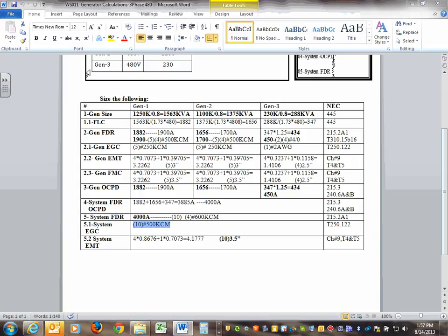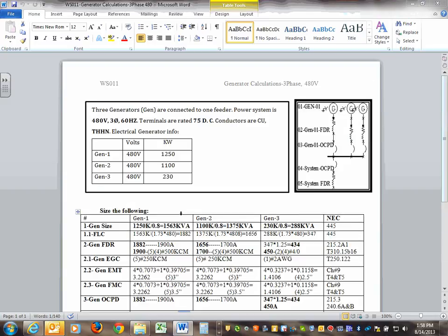Any questions about that? I know at that level, guys, we're engineers, we can kind of play with the numbers a little bit. I could have lowered this, see this one here, I could have adjusted to 3900 amps and sized my conductor to 3900 amps. But at that level, you take full advantage of a plug that is rated for 4,000 amp, and my switchgear is 4,000 amp, so it's easier to continue with the 4,000 amp. So there's a few rules here. Any comments, guys, about this? Too much, too little?